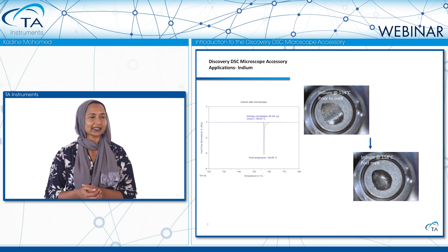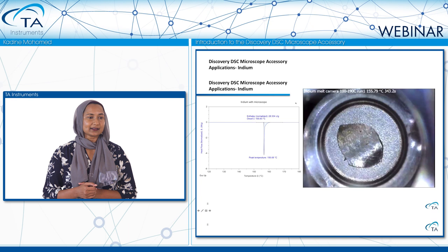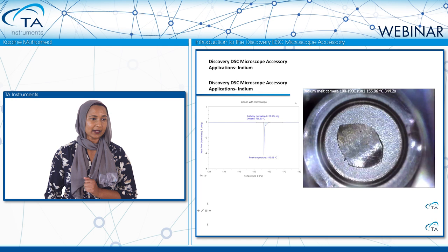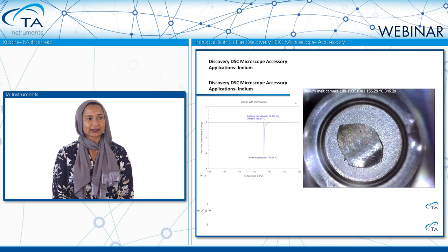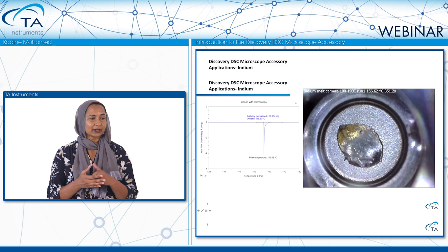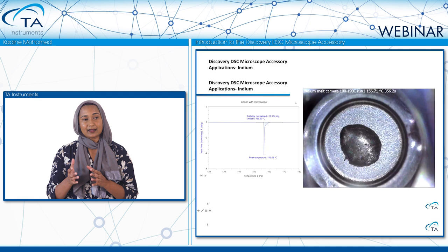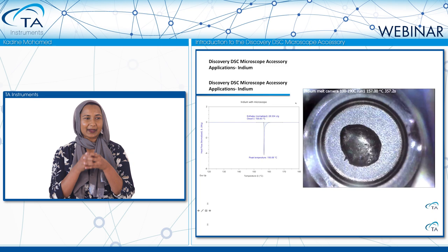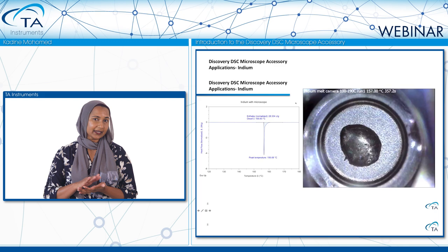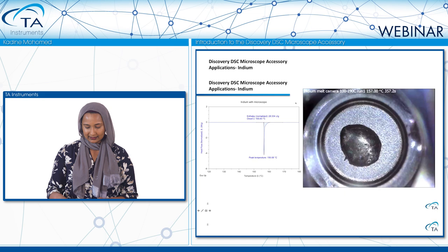We also see images captured both before and after the melt. A video clip shows the temperature beginning at 156.29 degrees. As the temperature ramp proceeds, the indium sample begins to move, and by 156.8 degrees, the material has undergone a melt transition. The sample didn't flow to cover the bottom of the pan — it remained in a glob. This illustrates why it's important to cut the indium thin and ensure good contact with the pan, to obtain the best enthalpy measurement.